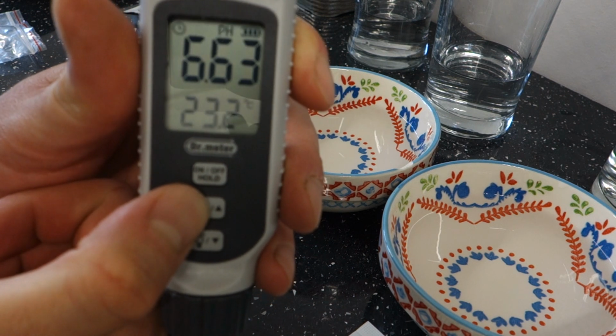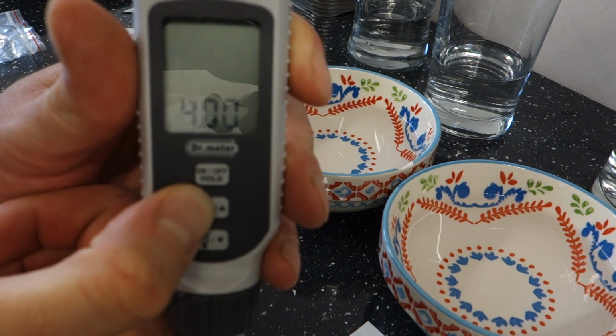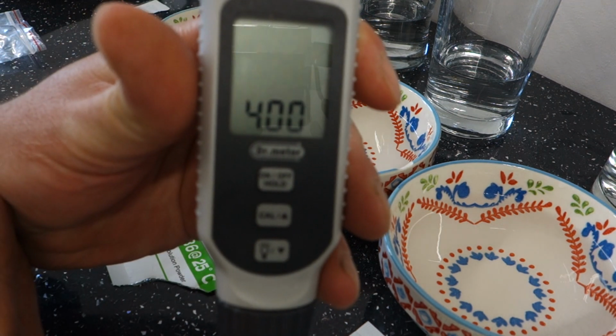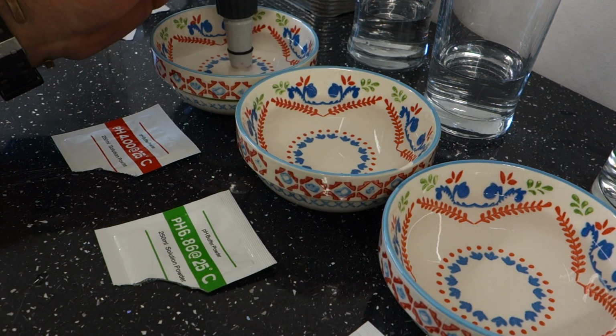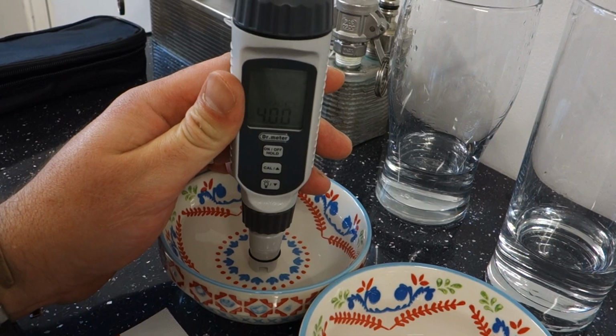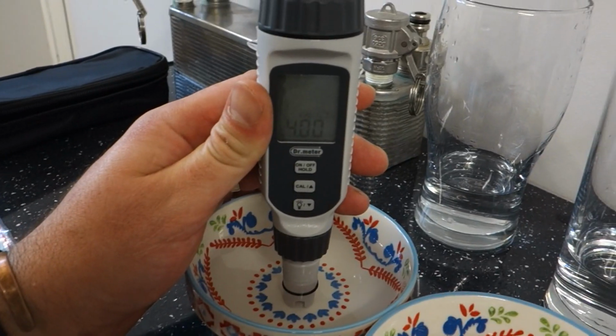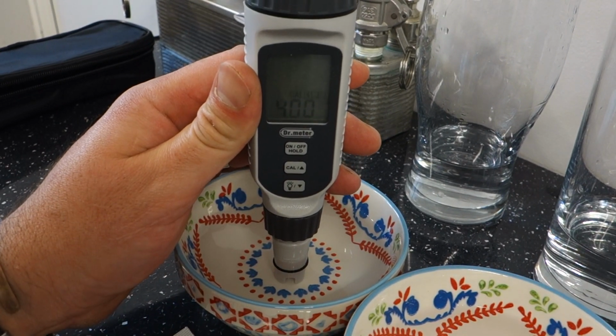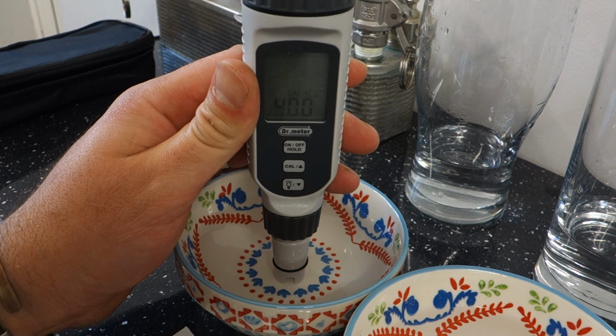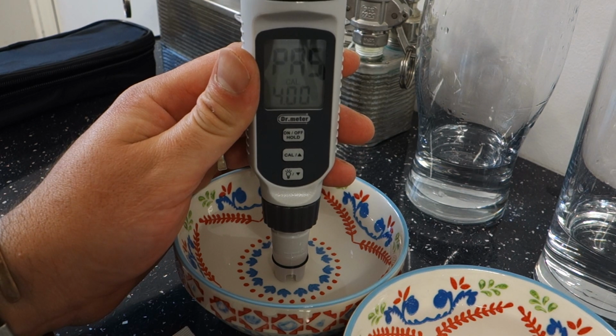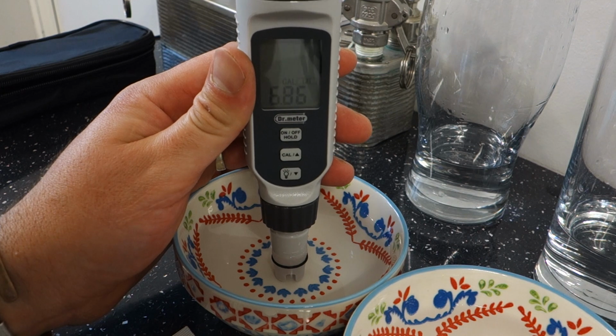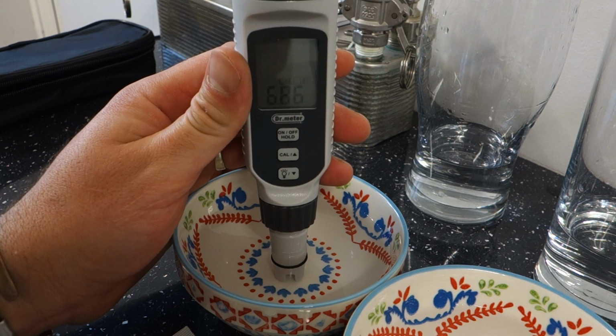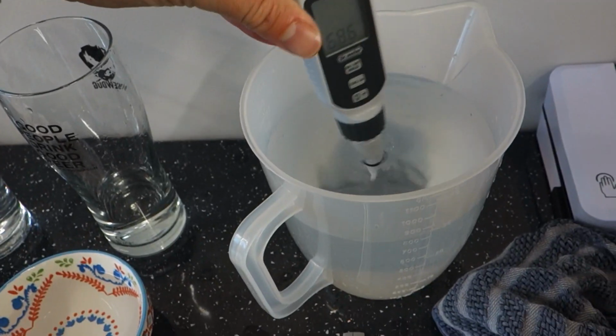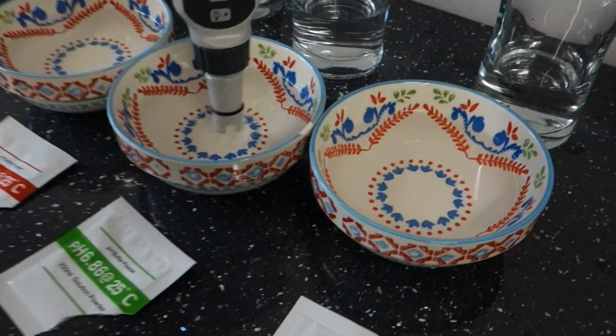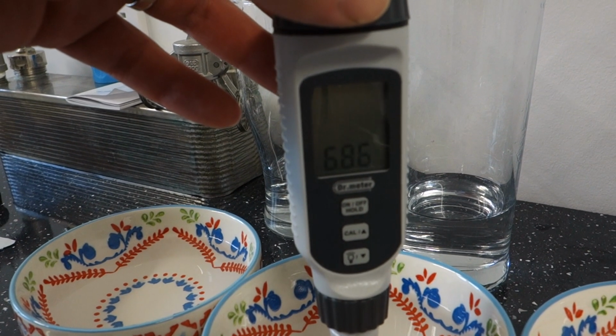And I'm going to press and hold the cal button. There we go. See, it's flashing. It's reading 4.00, and you should see that eventually, after it's done running the calibration, pass. So now it's moved on to the next one, the 6.86. So rinse this in here, give it a rinse, and move it on to the next. Oh, the lighting is atrocious.